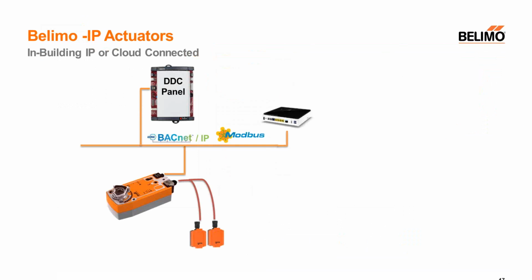And moving to the next product, we have a dash IP line of actuators that we've had for about a year now. Those are similar to the mod actuators in that they support both BACnet or Modbus. It's selectable, but they're the IP or Ethernet variants of both of those protocols. So instead of a 2-wire RS-485 network in your building, you leverage the IP network. And the IP actuators also support an additional sensor. So instead of just one sensor, you can hook up 2. But you have the same capability of sending a signal to the actuator via that bus technology, getting feedback back, getting sensor values back.